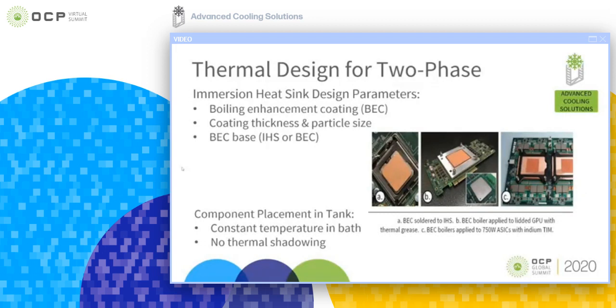The major advantages of two-phase immersion cooling would be the constant and isothermal temperature environment. So it provides a much more even thermal profile in the tank as compared to other cooling techniques. And there is no thermal shadowing because all the components in the tank will be at the same temperature, which is the boiling temperature of the fluid. So there's also no thermal shadowing, right? So there is no thermal shadowing, yeah. It's the constant, it's the isothermal temperature environment.